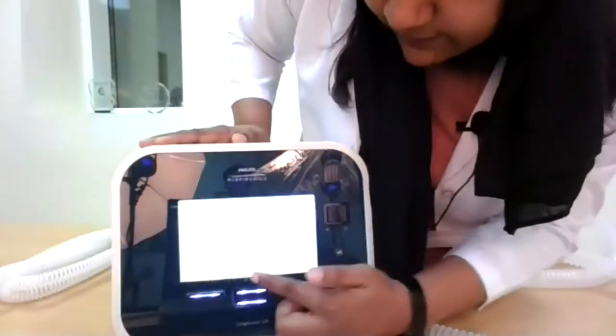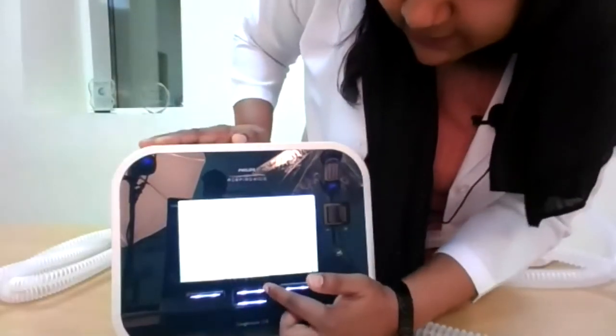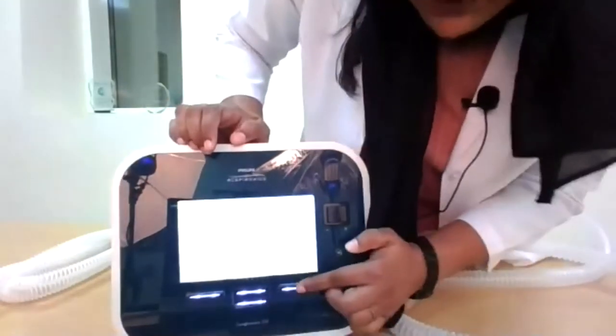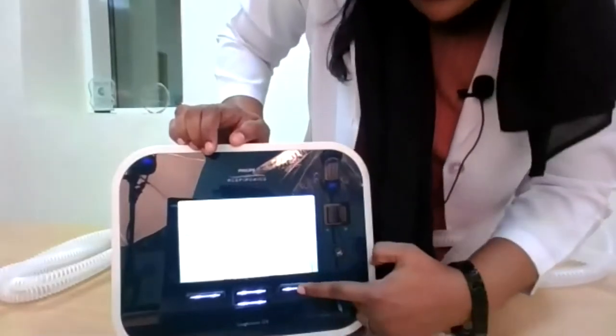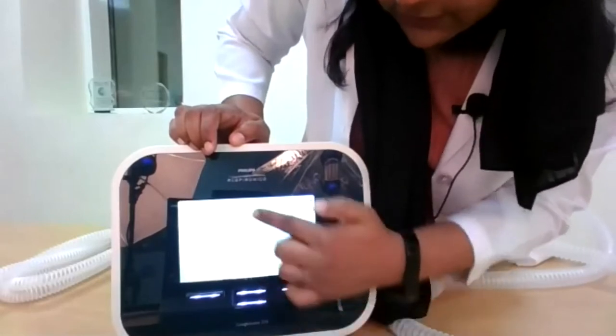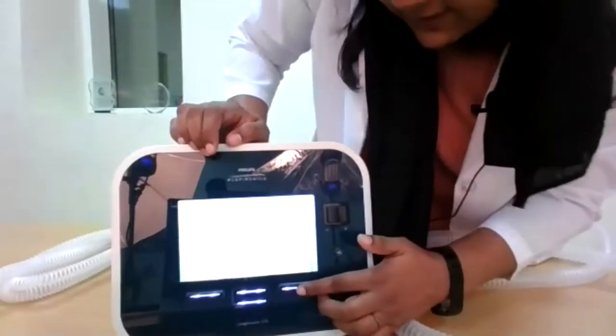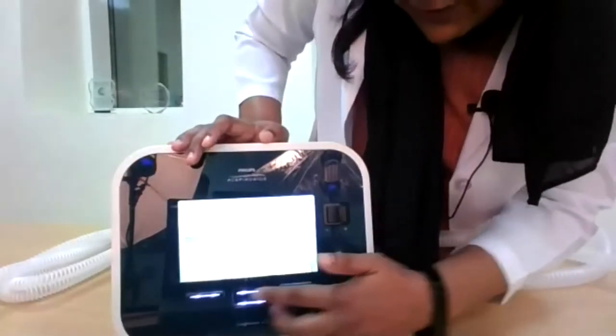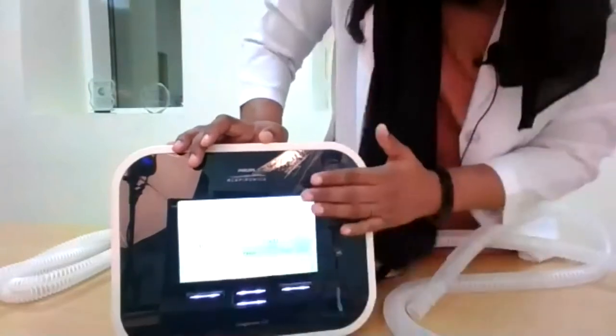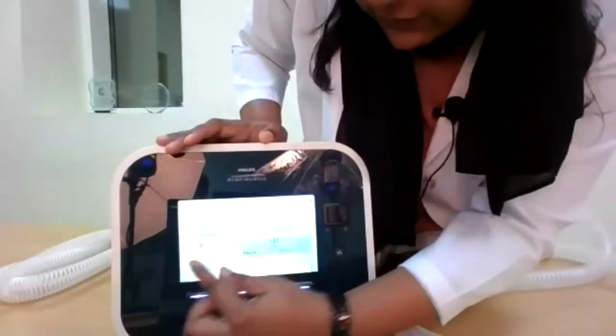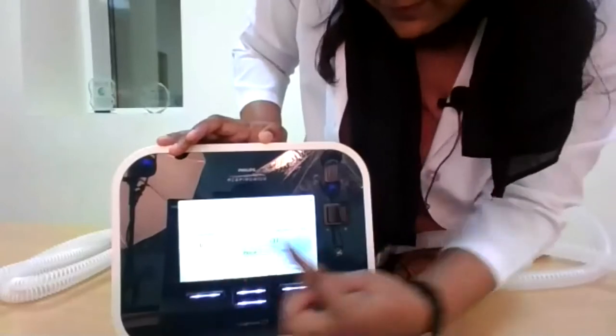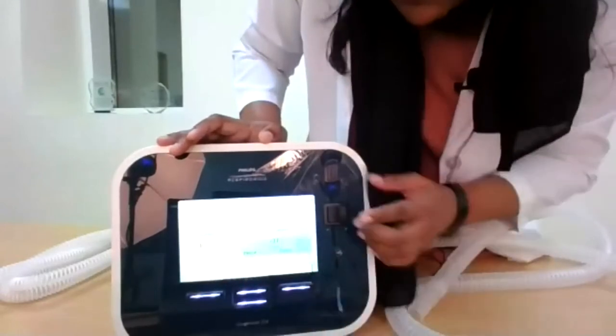You need to click on the settings option and you can see the highlighted button here. The preset is already selected as 3. Next, you can see the mode option. If you need to modify the mode option, you just have to press the modify button here and navigate the options. Now we can see it has been selected as manual mode, and once it is selected, you can press the OK button here and then finish. Now the patient is on manual mode. You can see the exhale pressure, expiratory pressure, as well as the inspiratory pressure here.